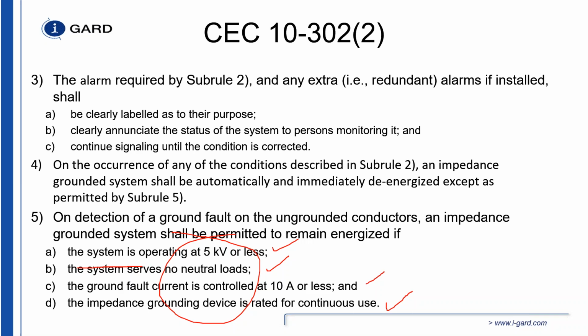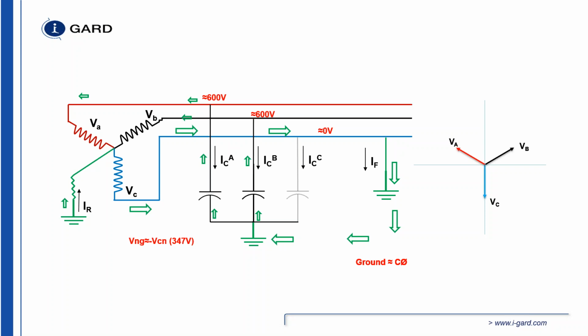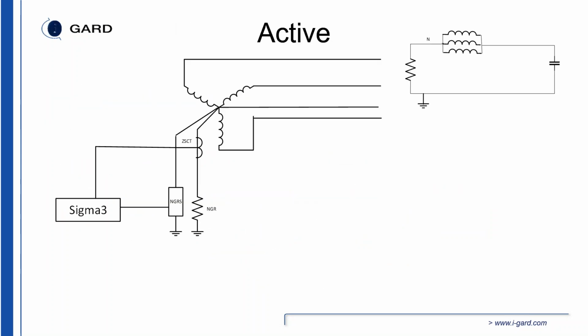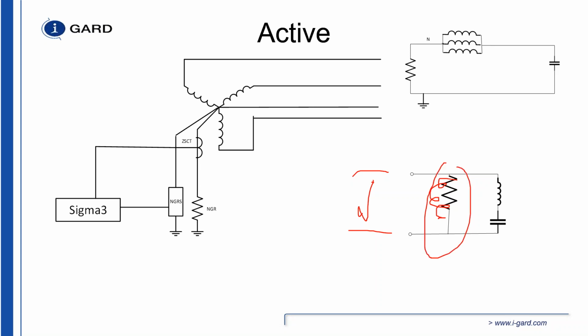If we're putting an inductor here, now we have an inductor in parallel with an inductor. So in active mode, it might be difficult. If these two inductances are somewhat similar, we're going to end up with half of the inductance here. So it's a little trickier to do that because the impedance of the neutral grounding reactor is frequency dependent. And it depends on the variation of the impedance of the transformer coils and the neutral grounding reactor. If there's a wide gap between them, yes, we can do it in active mode. I have never tried it. But again, in passive mode, it can be done.